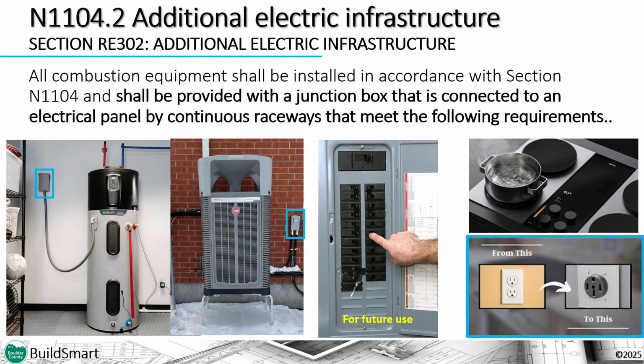We covered additional electrical infrastructure in the new home compliance presentation, but again, BuildSmart does not prohibit the use of fossil fuel mechanical equipment. It does require, however, that additional electrical infrastructure be added next to any installed fossil fuel appliance, such as the furnace, hot water heater, and cooktop. This includes properly labeled reserve space in the electrical panel for the properly sized breakers that can serve the future equipment. This future proof of the home allows the consumer more choice when the mechanical appliance fails or needs to be replaced.